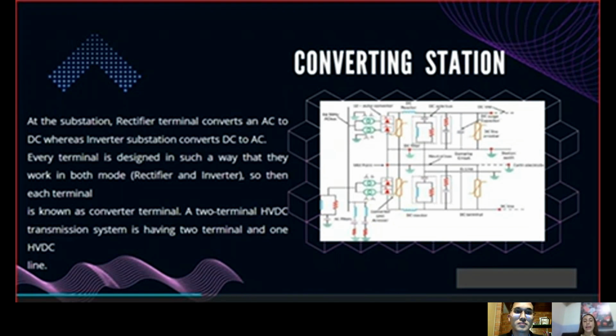Every terminal is designed in such a way that it works in both modes, rectifier and inverter. So each terminal is known as a converter terminal, and a two-terminal HVDC transmission system has two terminals and one HVDC line. The following figure shows a typical HVDC converting station.